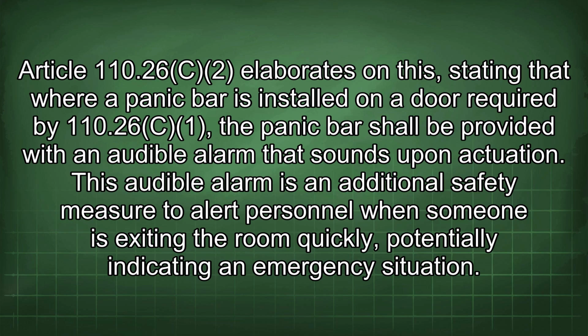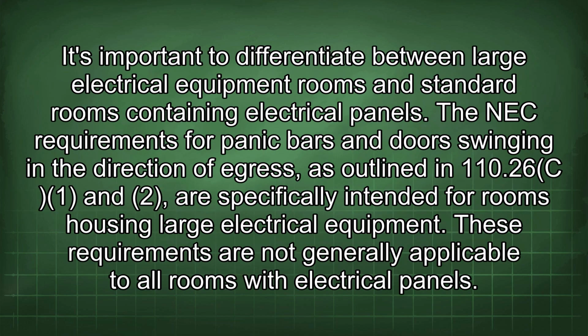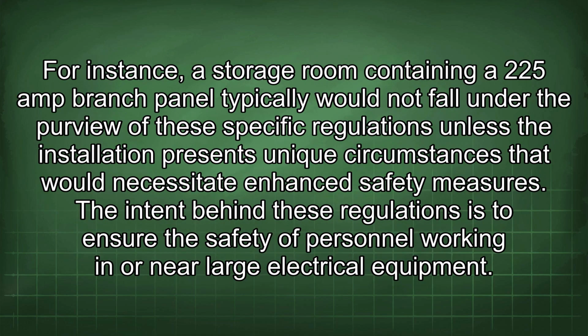an emergency situation. It's important to differentiate between large electrical equipment rooms and standard rooms containing electrical panels. The NEC requirements for panic bars and doors swinging in the direction of egress, as outlined in 110.26(C)(1) and (2), are specifically intended for rooms housing large electrical equipment. These requirements are not generally applicable to all rooms with electrical panels. For instance, a storage room containing a 225 amp branch panel typically would not fall under the purview of these specific regulations unless the installation presents unique circumstances that would necessitate enhanced safety measures.